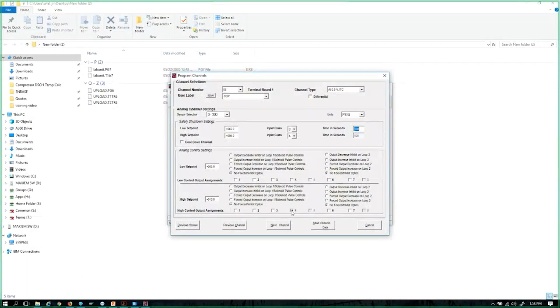In this case, what we're telling it is we want to turn on digital output 4 when the compressor oil pressure is equal to or greater than 10 psi. Why are we doing this? More than likely, what we're doing in the panel design is for a pre-loop pressure permissive.